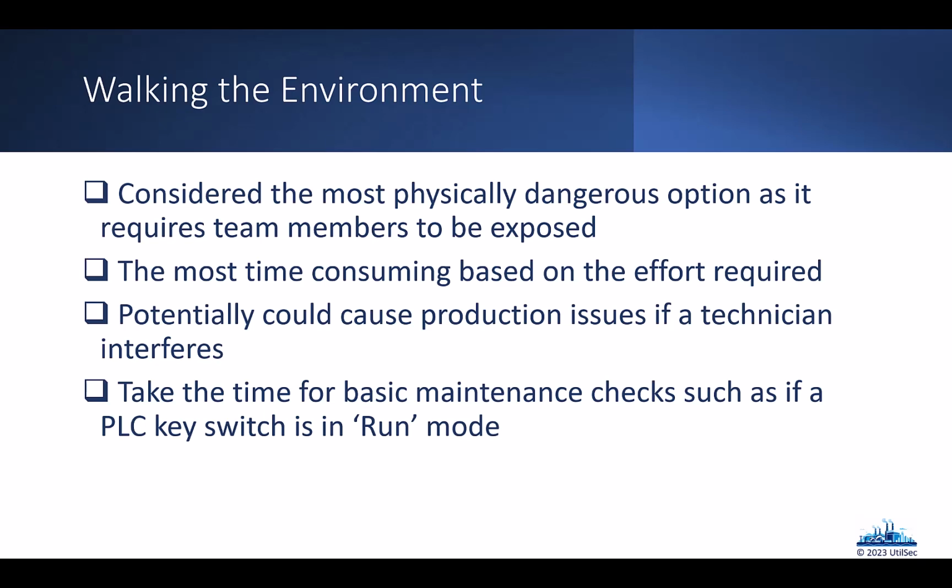And then what if somebody is tracing a cable and a cable accidentally gets disconnected or wiggled loose, and then we can cause production or availability issues within the site. Right? So there's definitely other risks as well at play. I do like the idea, though, if we do have somebody walking the environment, whether it's building an asset register or somebody doing maintenance, whenever they come across a PLC, one thing to keep in mind is to make sure we check to see that the PLC key switch is turned to run mode.